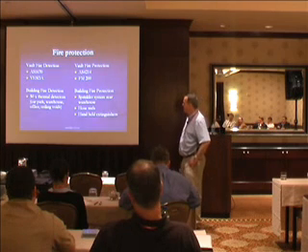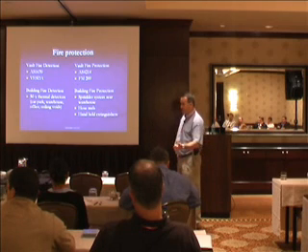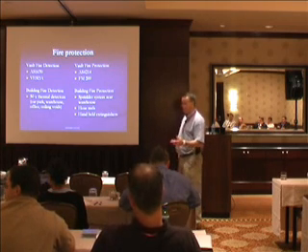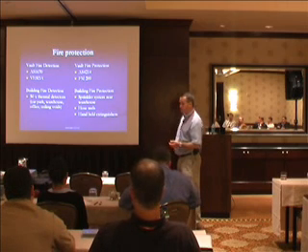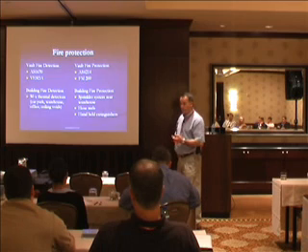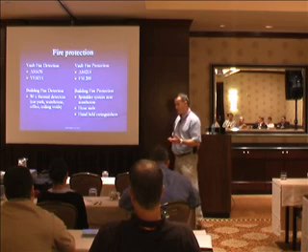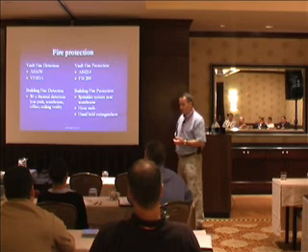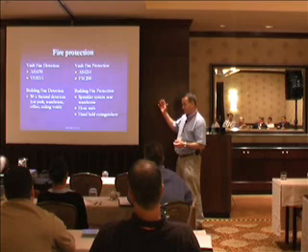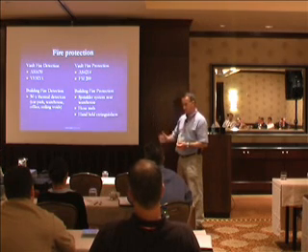On the fire protection, it's pretty standard vault fire protection. You're using Vesda for a detection system. Everyone know what Vesda is? We're going to use FM200 as a suppression agent. My personal belief is you need plenty of detection, but you don't really need an FM200 system. I believe that tapes don't burn. And we have nothing apart from the electricals, which we're shielding.